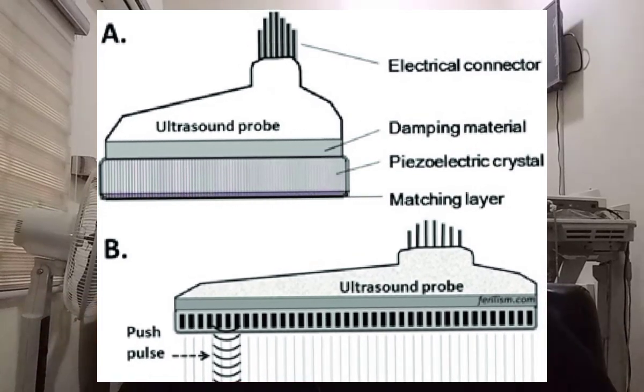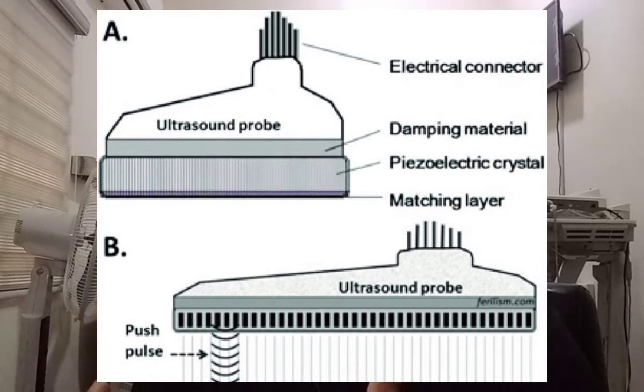In linear array transducers, a collection of active elements are arranged in a line. A linear array produces a sound beam by firing subgroups of elements — typically 8 to 10 elements — to produce the sound beam for each scan line. Each successive scan line is formed by switching or pulsing adjacent subgroups of elements in a sequential fashion along the length of the array.